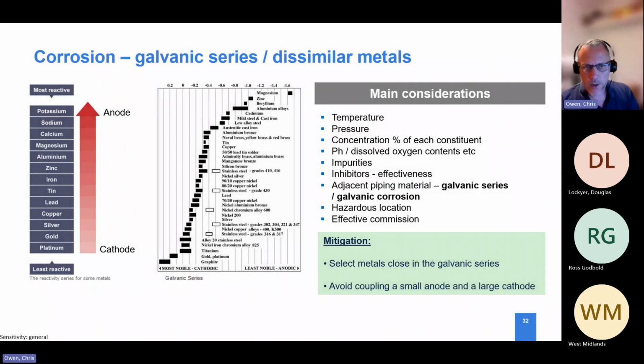So at the start of the presentation, I made reference to what was called galvanic corrosion. Now, galvanic corrosion has become more and more of a problem as far as I'm concerned in building services. And this is because historically we used to see a lot of people use traditional thick wall tube. When thin wall precision tube came into the market, it came across as being a much simpler, easier to use product. Certainly its speed of jointing and installation was a lot faster, so speed of work, time savings. Lightweight tubes are easier to carry around, and it was presented as, dare I say, a low skill installation, because you could just crimp the joints. You didn't have to look at roll grooving or the skill of threading and making up a leak tight screwed and socketed joint. The problem was, as we talked about in some of the earlier slides, corrosion became a big issue and these tubes started to fail very quickly, and it was more to do with the commissioning, which we'll talk about in a bit.